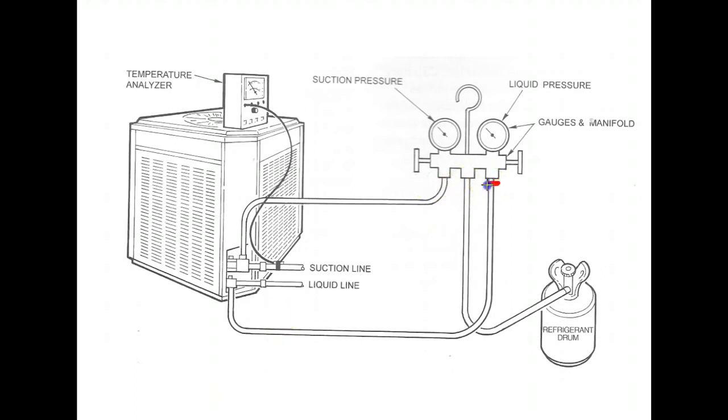This needs to be a little bit loose. And as soon as you start to get refrigerant purging out of the fitting there, you know that the line has been purged and you're going to tighten that back up.